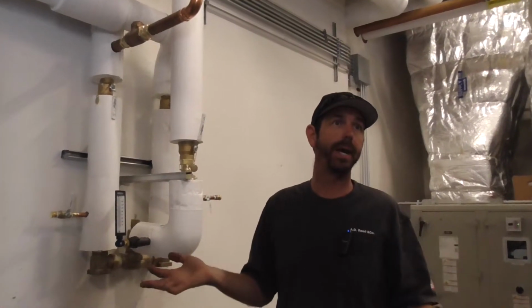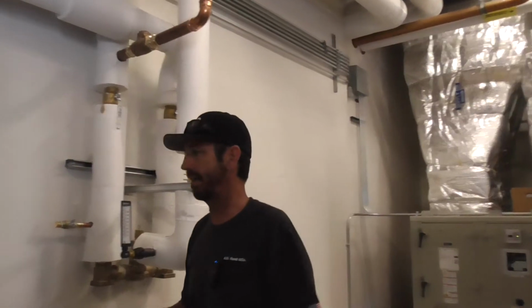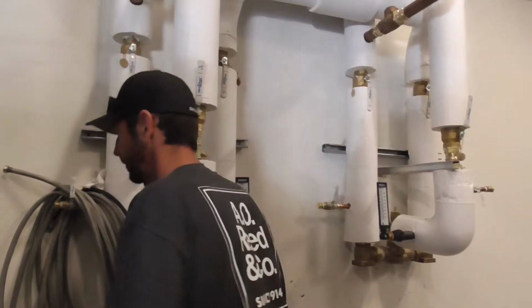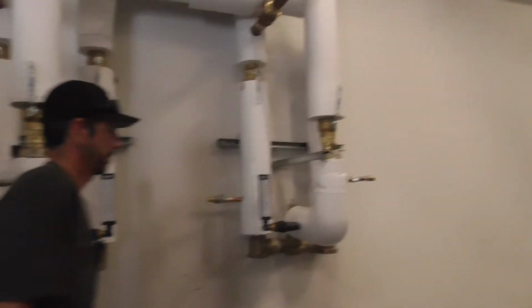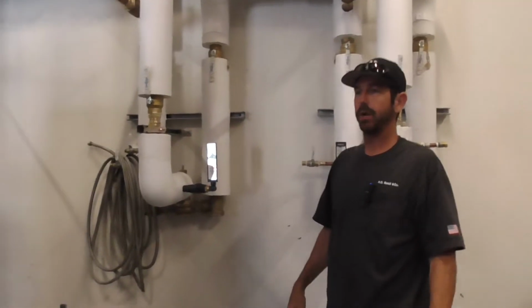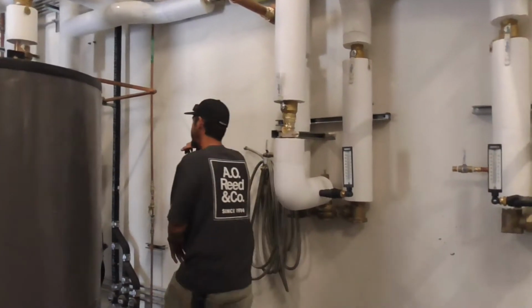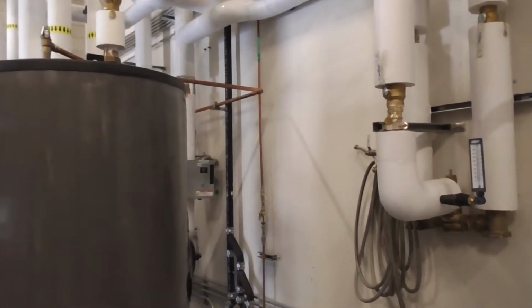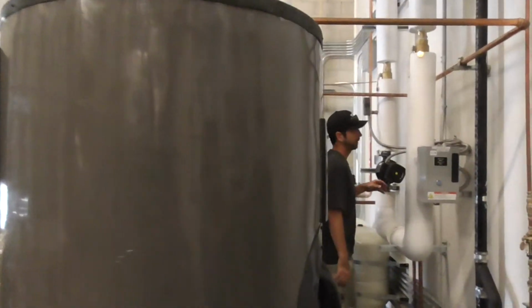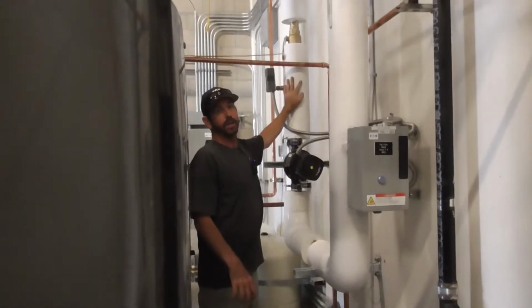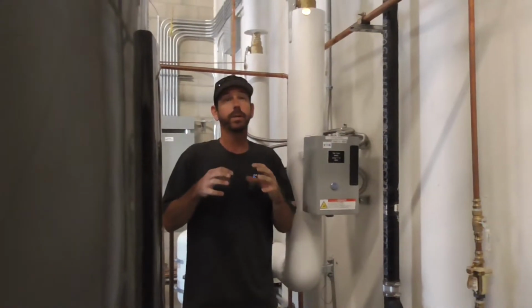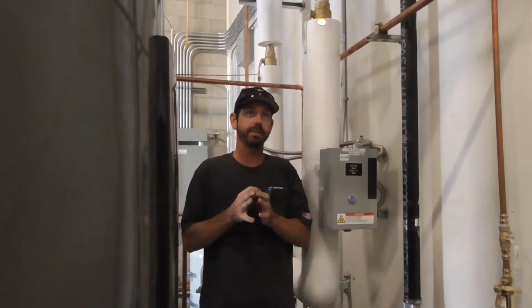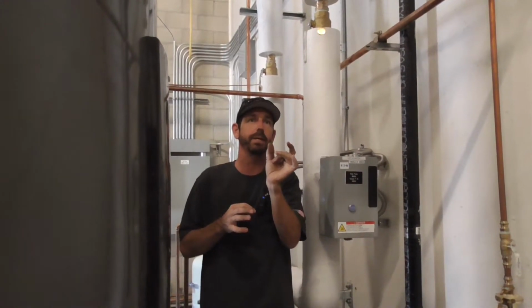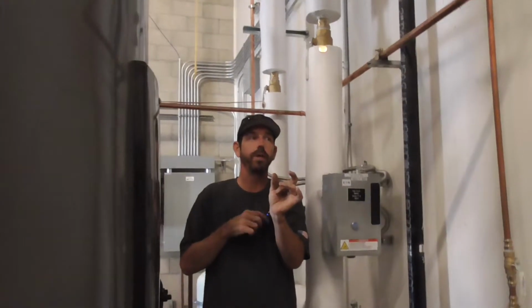Okay, so this building's so big that in no load conditions, we have a domestic hot water return loop. So under no loads, we have a circulating pump over here. It's drawing water back from the building, okay? When we get up higher, I'll show we have the Caleffi thermostatic balancing valves, so they're off temperature. Have you ever experienced balancing valves off temperature? No. So this one has a bellows inside of it, and the bellows can expand or contract depending upon its temperature. Okay?